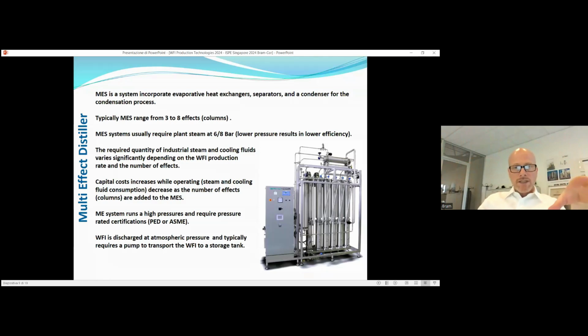It is a pressurized machine, as I was anticipating before. So the higher the pressure of industrial steam for heating you give, the smaller the machine is, and the lower the pressure you give, the less efficient the machine itself is.